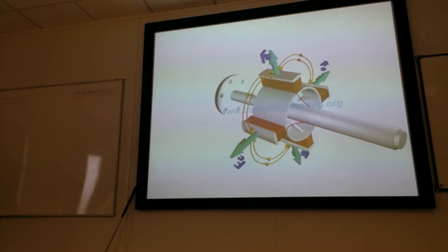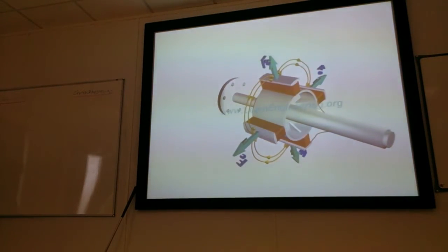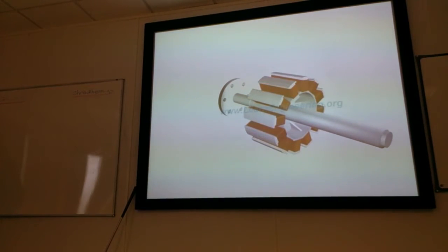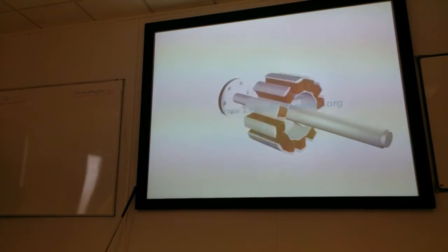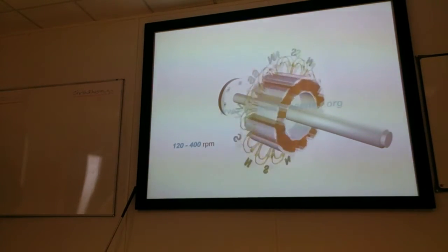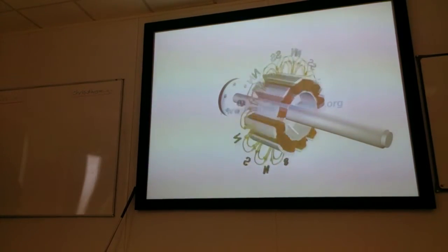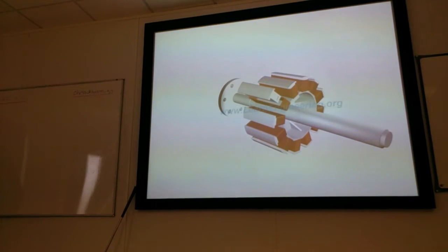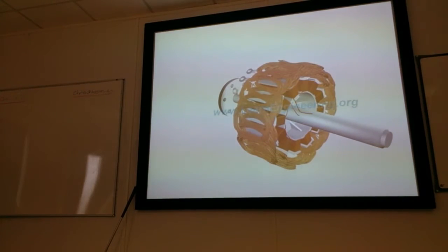Such huge RPM will induce a tremendous centrifugal force on poles of the rotor, and it may fail mechanically over time. So salient pole rotors are generally having 10 to 20 poles, which demands lower RPM. Or salient pole rotors are used when the prime mover rotates at relatively lower RPM. Pole core is used to effectively transfer magnetic flux, and they are made with fairly thick steel lamina. Such insulated lamina reduces energy loss due to eddy current formation. Armature winding of 3-phase 12-pole system is shown here.